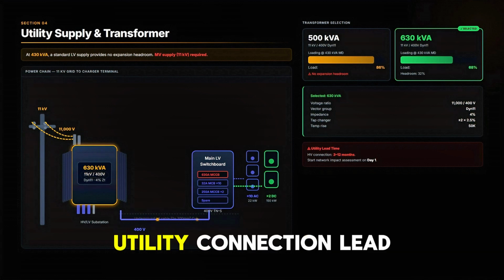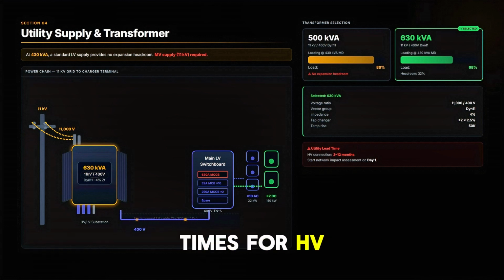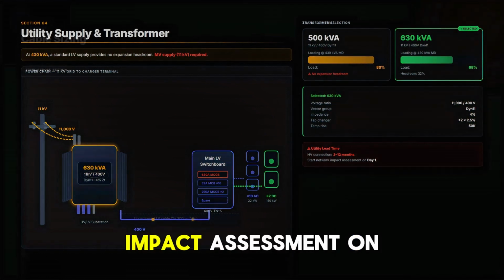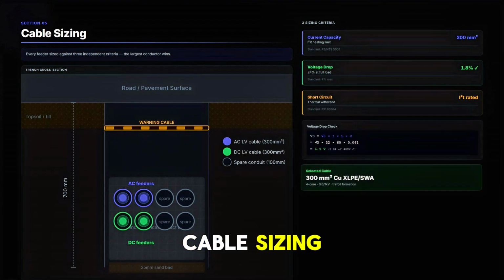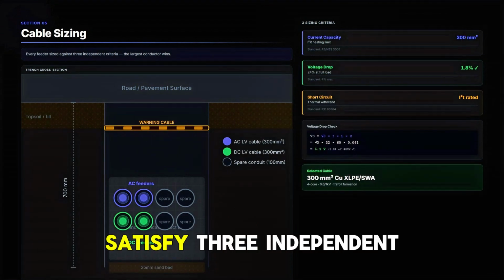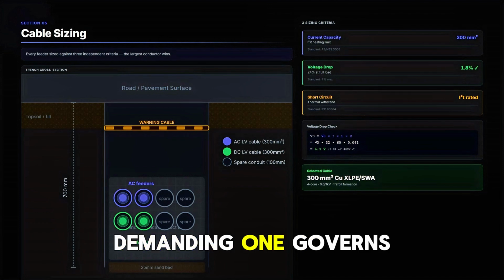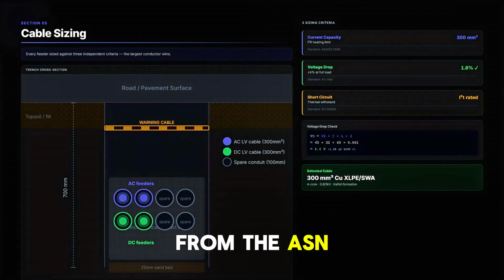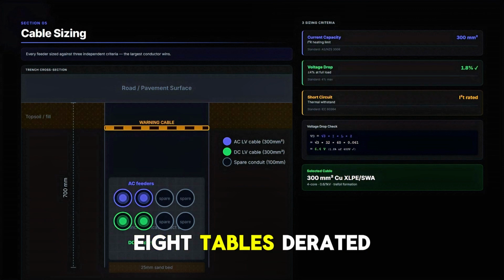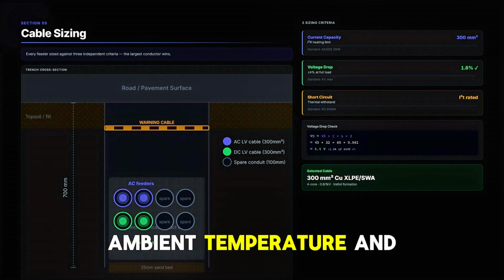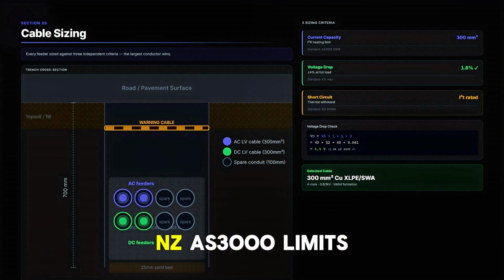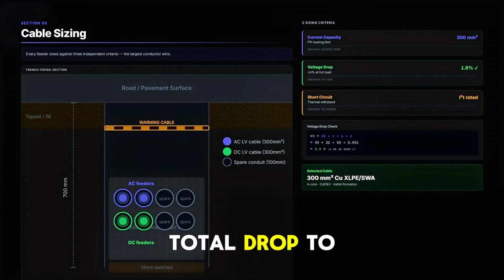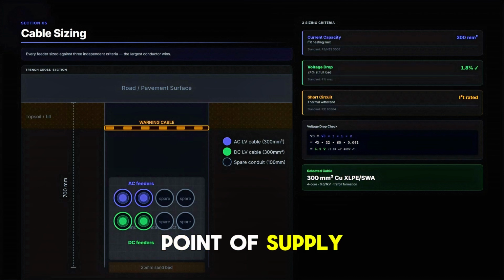One important note: utility connection lead times for HV supplies typically run 3 to 12 months. Start the network impact assessment on day 1 of the project. Cable sizing: every cable in the system must satisfy 3 independent criteria, and the most demanding one governs. Current carrying capacity from the AS/NZS 3008 tables, derated for installation method, ambient temperature, and grouping. Voltage drop, AS/NZS 3000 limits. Total drop to 5% from the point of supply to the load. We target 2.5% on the main run, 2.5% on the sub-circuits.